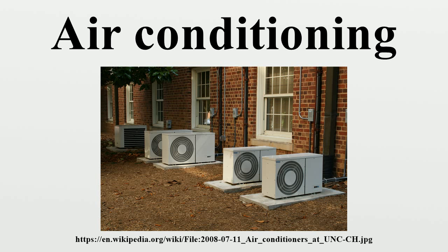Operating principles. Refrigeration cycle. In the refrigeration cycle, heat is transported from a colder location to a hotter area. As heat would naturally flow in the opposite direction, work is required to achieve this. A refrigerator is an example of such a system, as it transports the heat out of the interior and into its environment. The refrigerant is used as the medium which absorbs and removes heat from the space to be cooled and subsequently rejects that heat elsewhere.